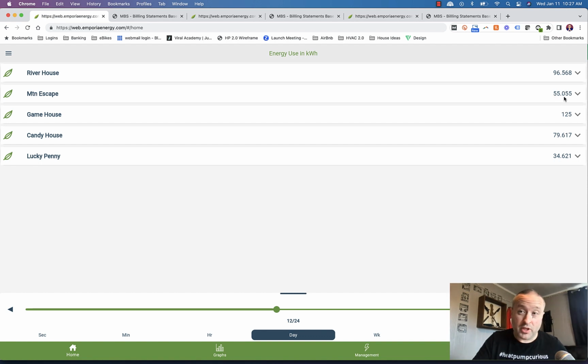It also has a larger heat pump. The Game House used a bunch of juice that day, 125 kilowatt hours. Now, this isn't actually totally obscene. One of my clients bought the 5-stage carrier heat pump, which shuts the heat pump off below 2 degrees, and doesn't turn it back on until you get to 7. We spent a while below 2, so he ran a couple days. He had one day where he used 250 kilowatt hours. That was an expensive day - cost $35, $40 to heat the house that day.